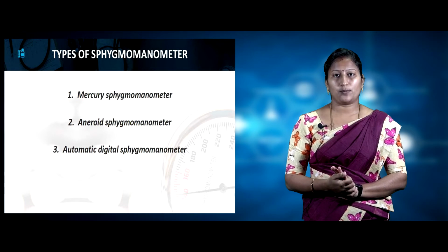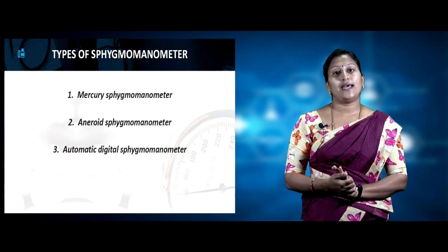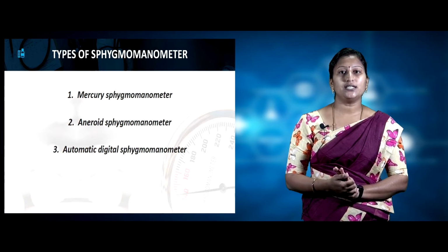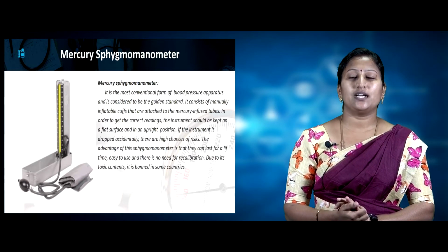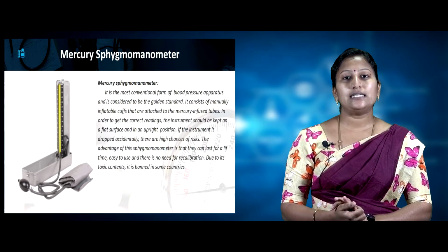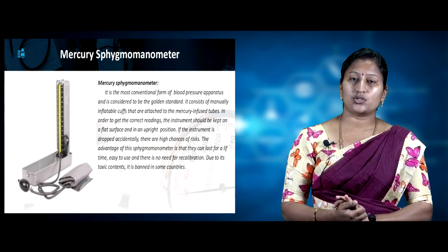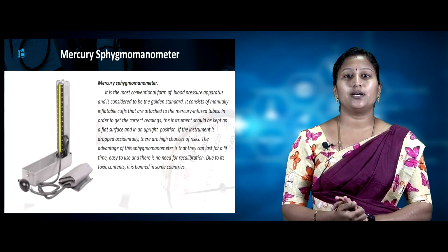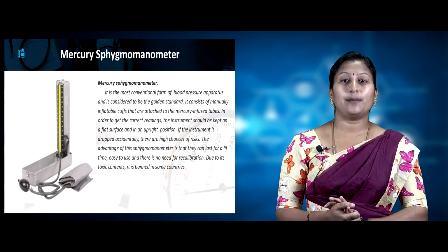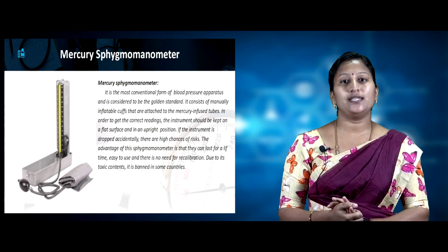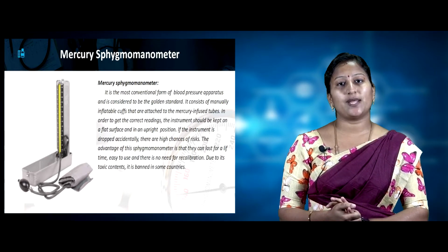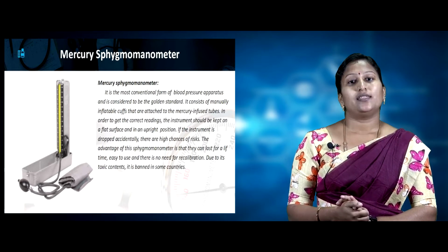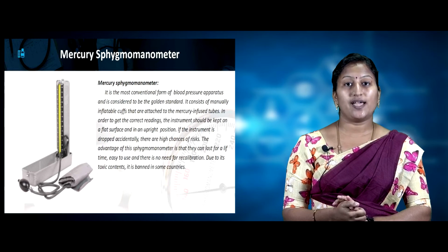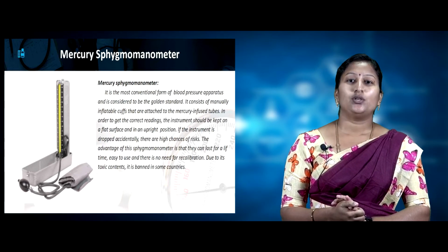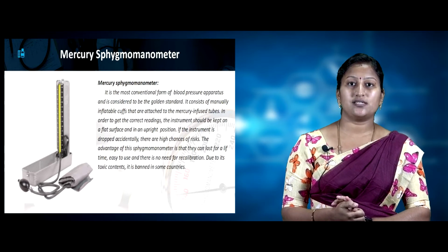There are different types of sphygmomanometer: mercury sphygmomanometer, aneroid sphygmomanometer, and automatic digital sphygmomanometer. Now let's see mercury sphygmomanometer. Mercury sphygmomanometer is a conventional blood pressure apparatus, and it is considered the gold standard. The instrument consists of a manually inflatable cuff connected to mercury filled tubes. In order to acquire the correct reading, the apparatus has to be placed on a flat surface and in an upright position. If the instrument is dropped accidentally, there are high chances of risk. The advantages of this instrument are that it is easy to use and need not be recalibrated. Due to its toxic contents, this apparatus is banned in a few countries.